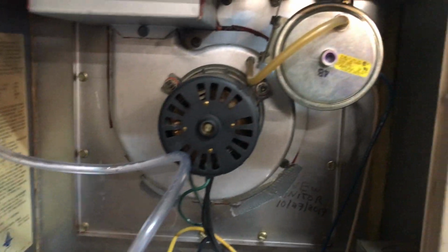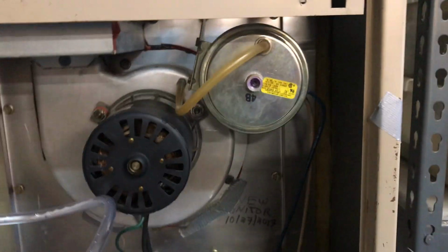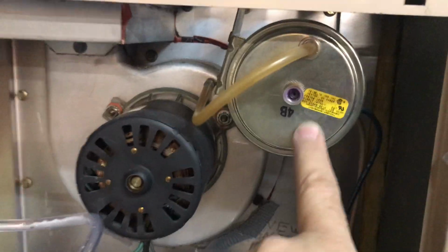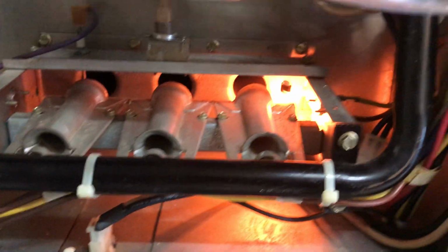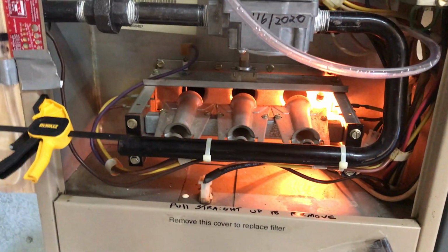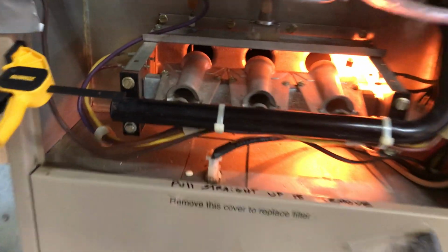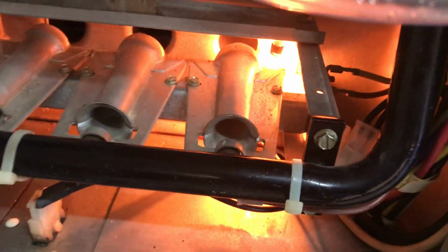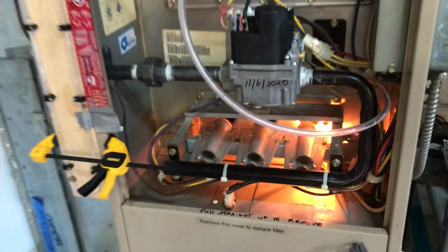So the venter motor verification comes on. It tells the computer whenever this little diaphragm closes, or opens actually, I think it is. No, it closes on the vacuum. The hot surface igniter gets signaled to turn on. That'll take a little bit. It'll get really, really hot. It would ensure that when it gets hot enough, there's a temperature sensor over here, and then that'll trip the computer, tell it to open the gas valve, and boom, you have ignition.